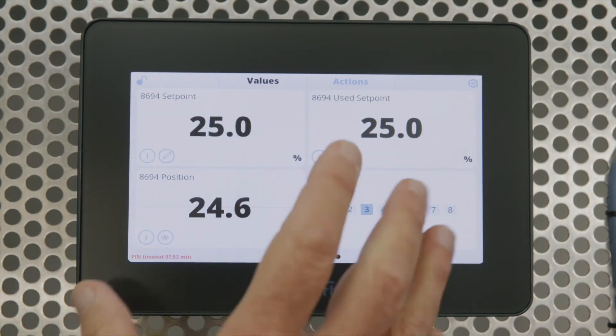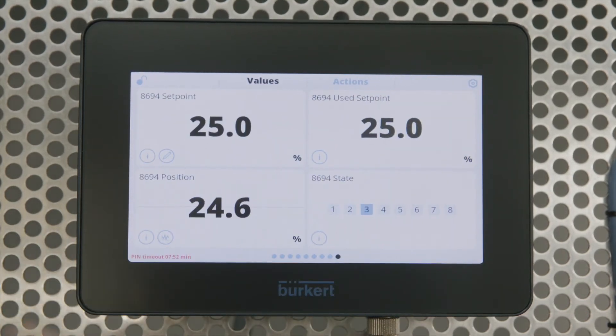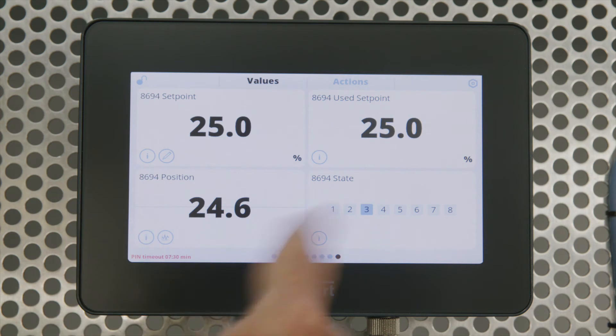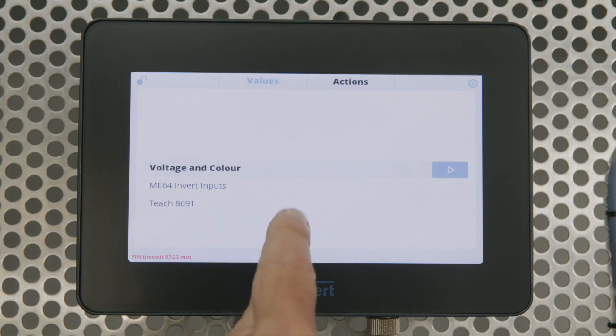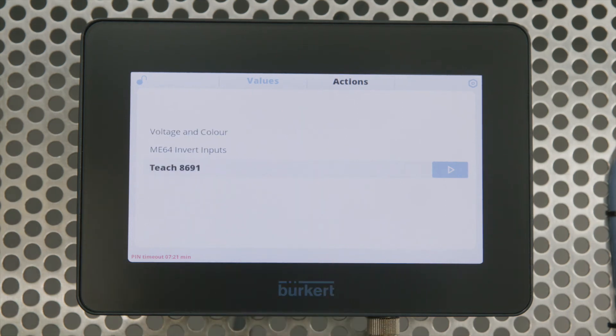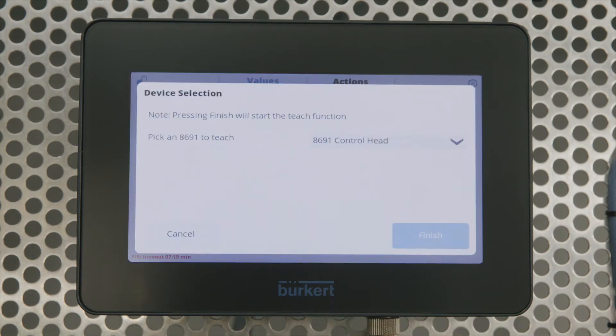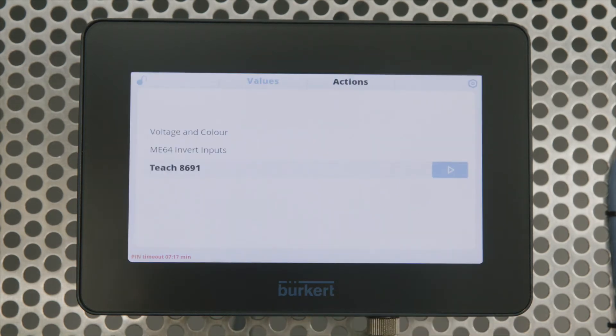The display can also change colour if you go outside a parameter. There's a nice feature called Actions where we can go in and change things like the colours. As an example, if I want to teach a valve, I can go in there and hit Teach on a control head — this actually calibrates an on/off valve and sets the feedbacks.